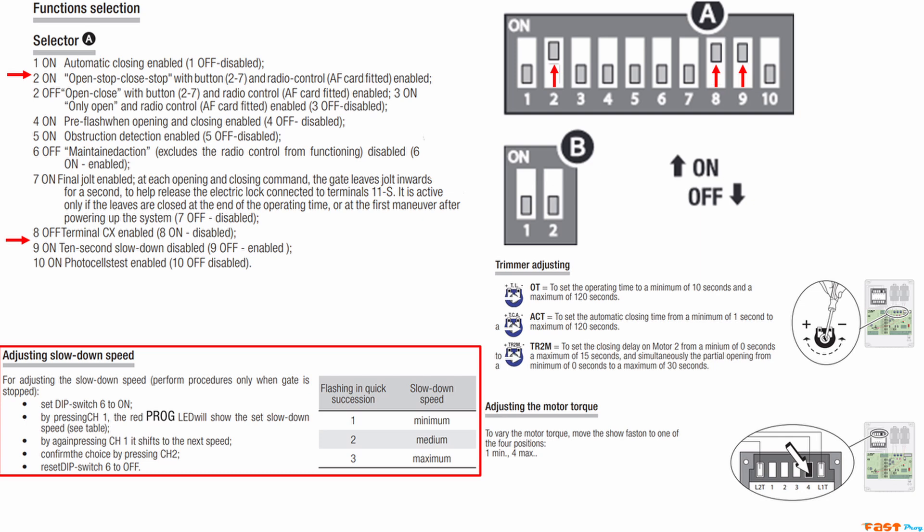Just so you know, when activated, the slowdown will kick in during the last 10 seconds of the operating time, which you can adjust using the TL potentiometer, we've set to about 30 seconds.